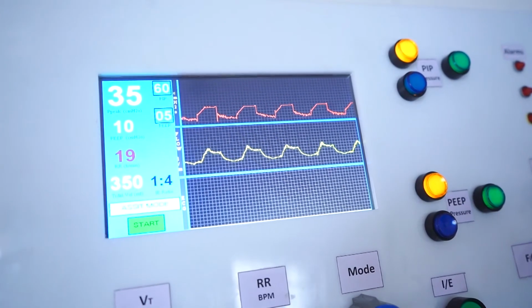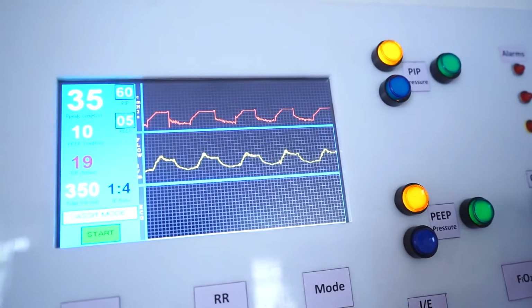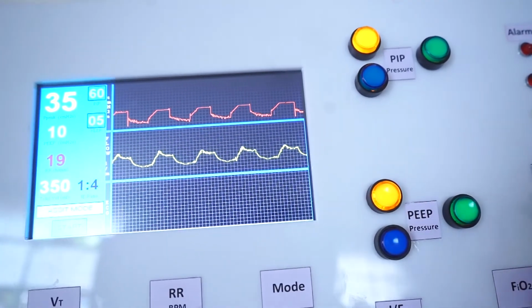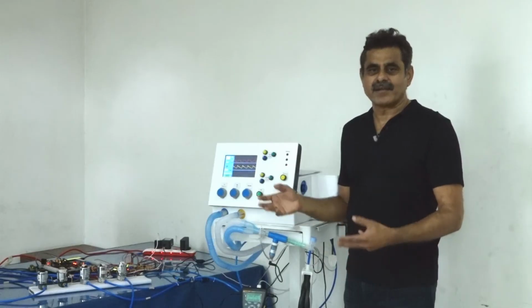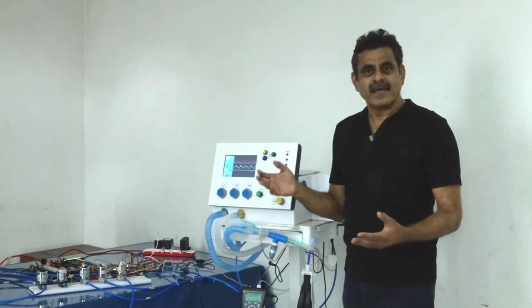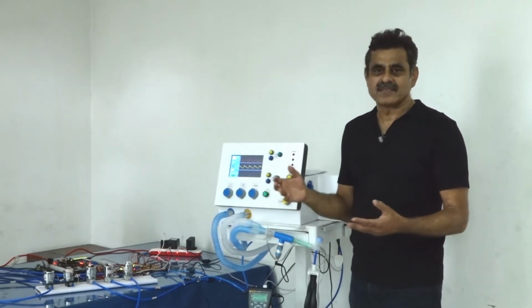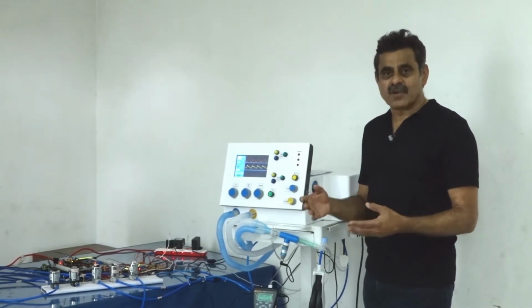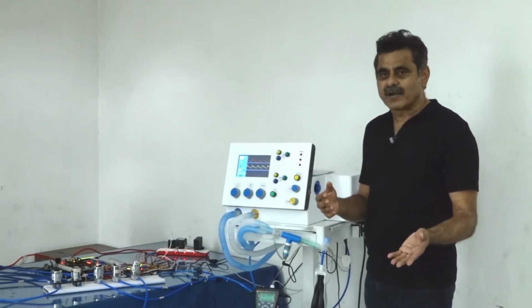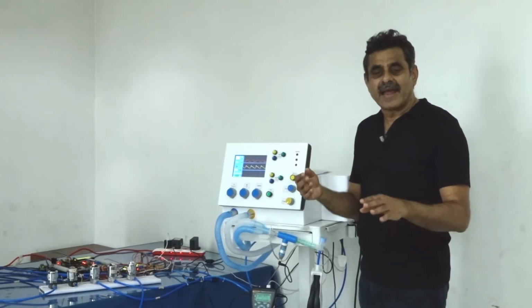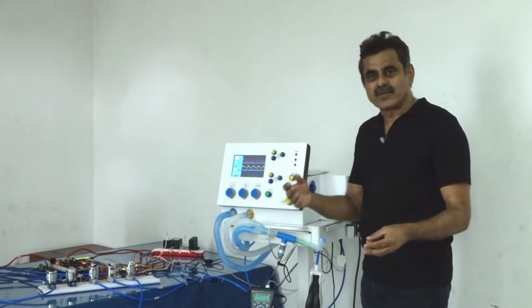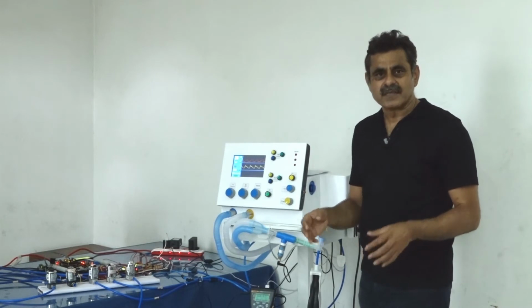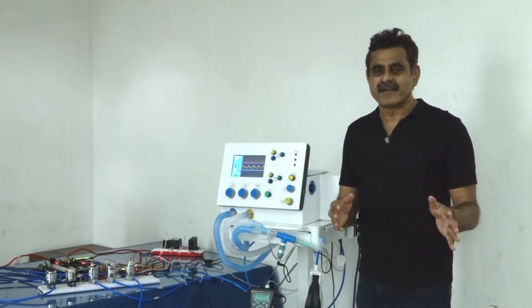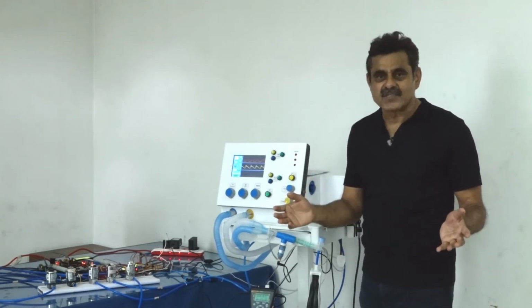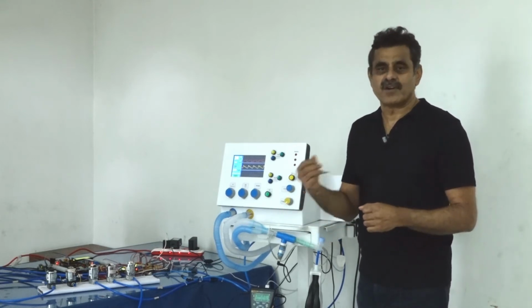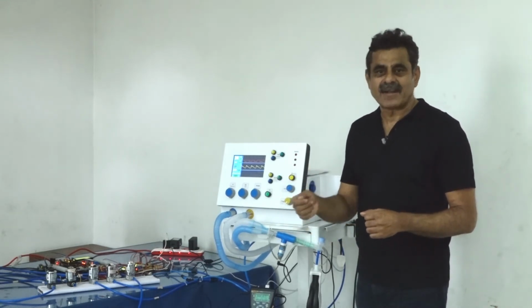Developing a ventilator requires multidisciplinary skills and experiences, because a ventilator is not a mechanical item, not an electronic item, not software. It involves hydraulics, pneumatics, mechanical, electrical, and software, where you have low-level and high-level programming, and in electronics you have analog as well as digital, and knowledge of flow controllers. In the mechanical part, not only pneumatics and hydraulics, we had special challenges because of the lockdown. Many parts were not available, so we had to make the parts ourselves.